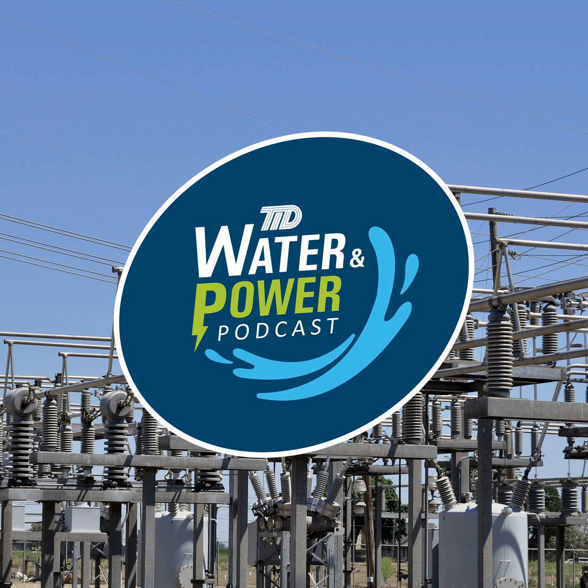Makes sense. And with that, we also don't have a maintenance breaker at Fairground, and it gets harder and harder to take outages on pieces of equipment. So if possible, we want to have a way of continuing to serve that load while working on the equipment. Okay. So we're going to give it a maintenance breaker with the transfer bus, essentially, to allow for that continued load serving capability. So there wouldn't be a break in reliability then. We would be able to do the work we need to do without taking that particular neighborhood or community out of power. Right. We would like to keep every single line in service if we possibly can.